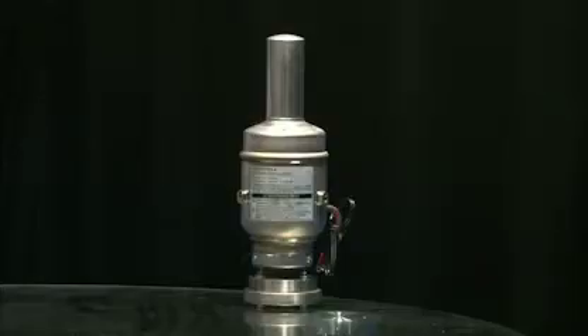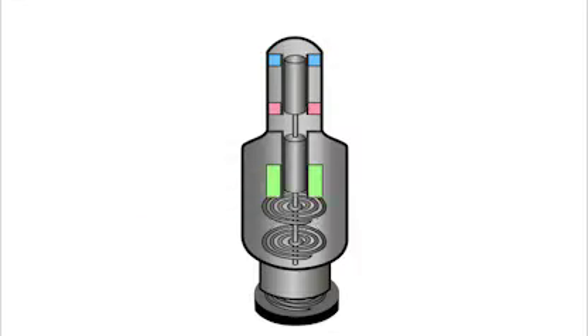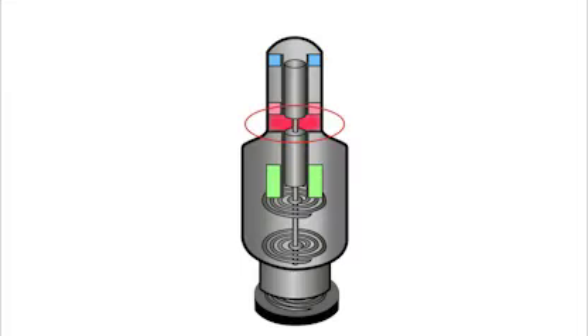Let's see how a Stirling cooler works. The Stirling cooler is filled with helium gas. When the pistons move, pressure rises creating heat. This heat is discharged using a heat exchanger. At the same time, the gas expands in the upper part of the cylinder and takes the heat from the surrounding atmosphere. It is through this mechanism that the upper part functions as a refrigeration system. By repeating this over and over, it is able to cool at a rapid speed.